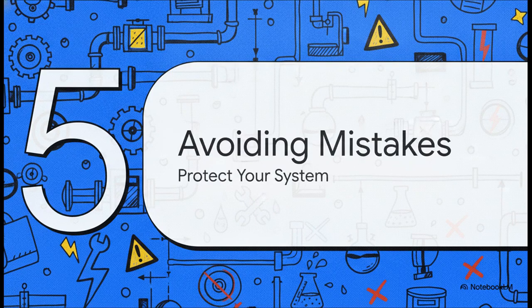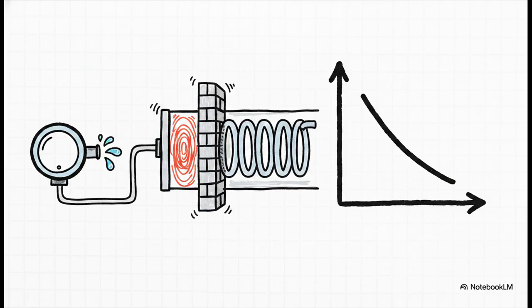And that leads us perfectly into Part 5, avoiding common dosing mistakes. You've got to constantly consult your pump's performance curve, guys. Why? Because high back pressure from the water system will severely reduce your actual chemical output. Think about it. A pump rated for 10 liters per hour at zero pressure might only deliver, say, 6 liters per hour when it's pushing against a 5-bar system. Overlooking this is pretty much a guaranteed one-way ticket to dangerous underdosing.